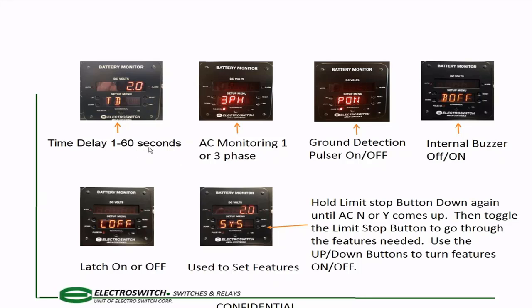Time delay, I say 1 to 60 seconds here, but it's really 5 to 60 seconds. So you put in the time delay and you use the up and down arrows to set it. That's to preclude spurious operation. If you get a momentary alarm, a spike or something, that precludes it.